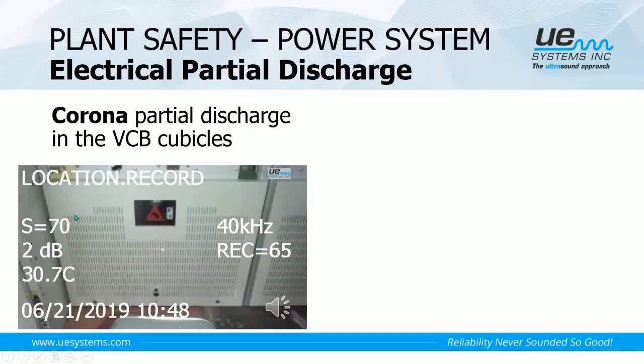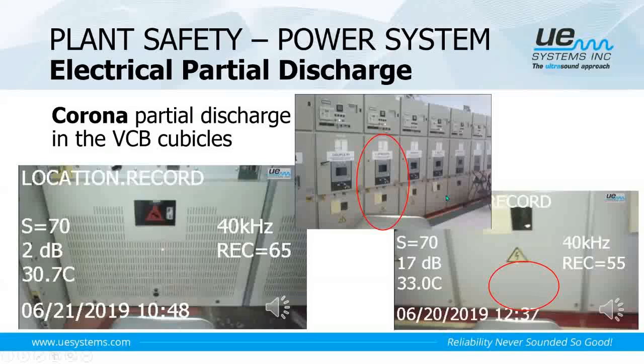We detect corona partial discharge at the VCB cubicle with 2 dB, a very low decibel level. The corona noise is steady and consistent. For a louder noise, the detection can be achieved from a further distance. This is a 17 dB corona detection. Without opening the panels, we can detect the partial discharge through the gap and the vent.